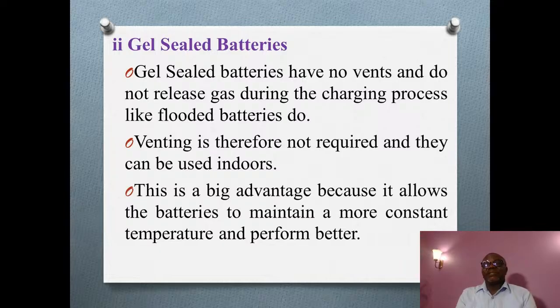The gel-sealed batteries have no vents and do not release gas during charging process, like the flooded one we talked about above. Venting is therefore not required and they can be used indoors. This is a very big advantage because it allows the batteries to maintain a more constant temperature and perform better. See, when the temperature rises, you lose energy in form of heat.